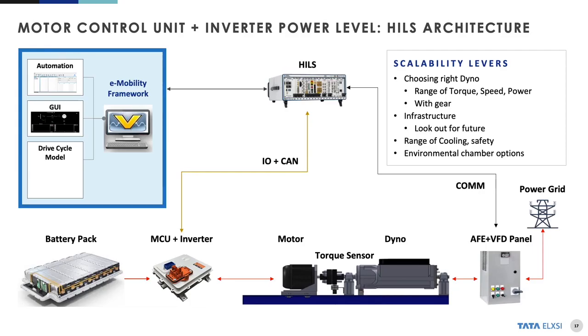Let us explain with an example how this system can be used for creating a loading effect on the motor. The HILS gives a required loading torque over a communication line to the VFD. The VFD converts this loading torque to a specific current value, and it tries to generate that current value from the dyno when it is made to act as a generator.